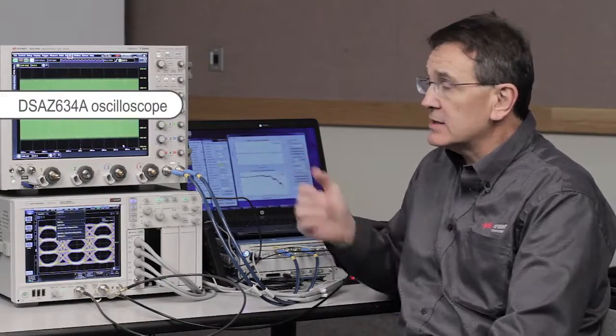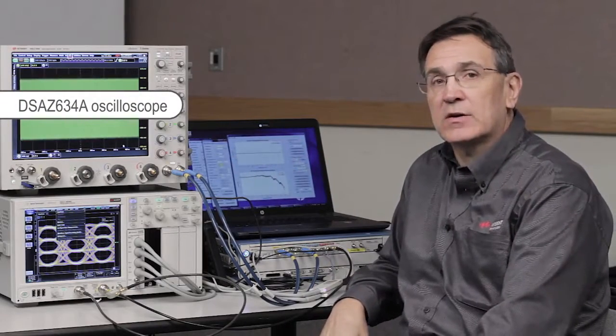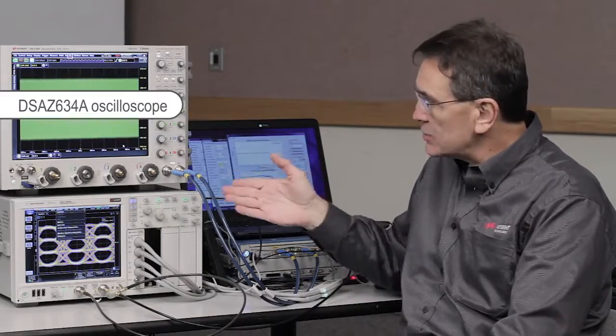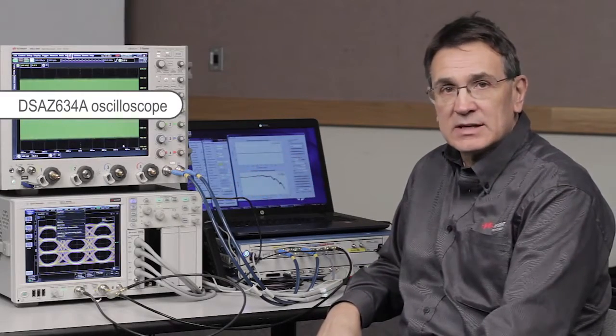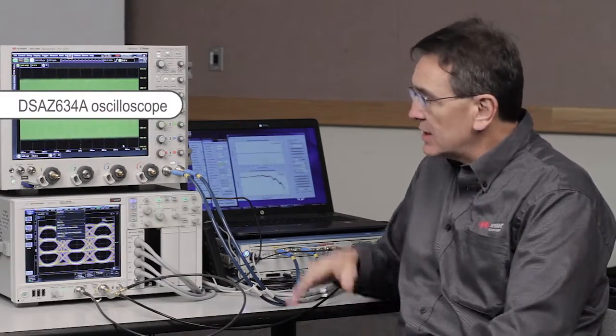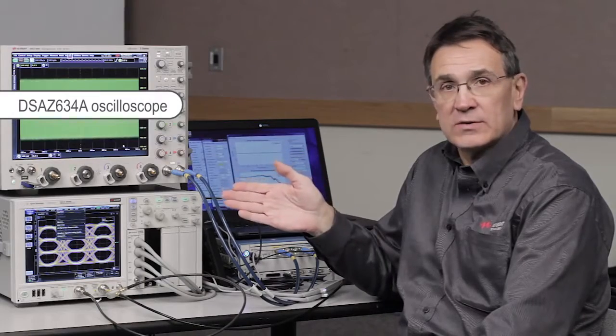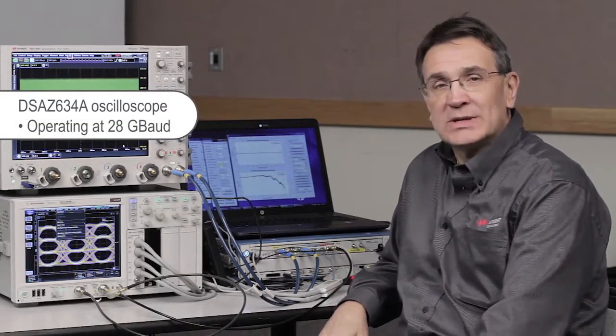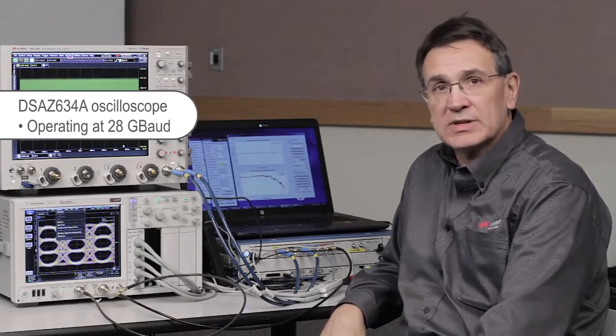We have a Keysight Z-Series 63 GHz oscilloscope, and we're using our real-edge channels that have full bandwidth out to 63 GHz to receive a signal, a PAM-4 signal, that's operating at 28 Gbaud, or 28 Giga symbols per second.